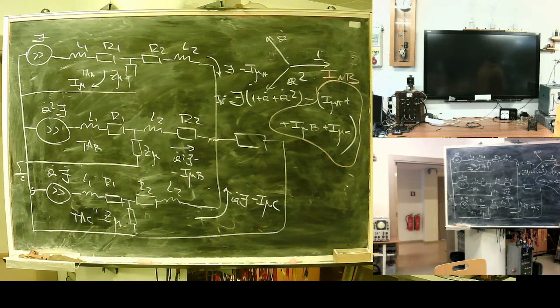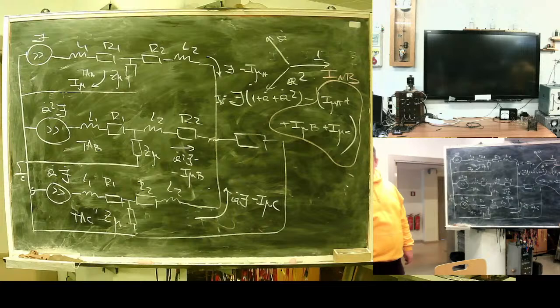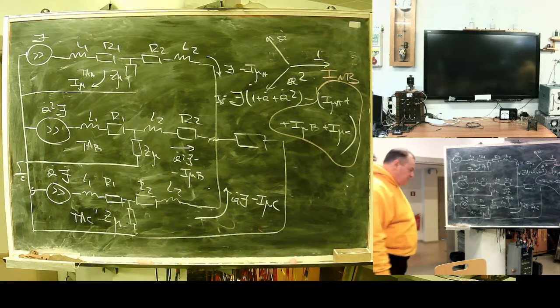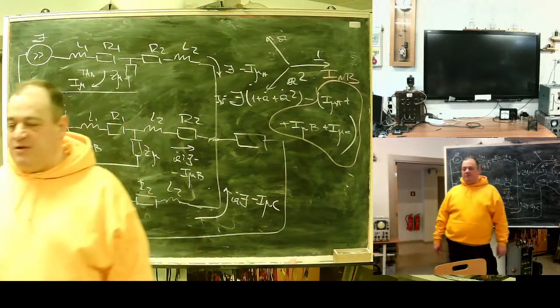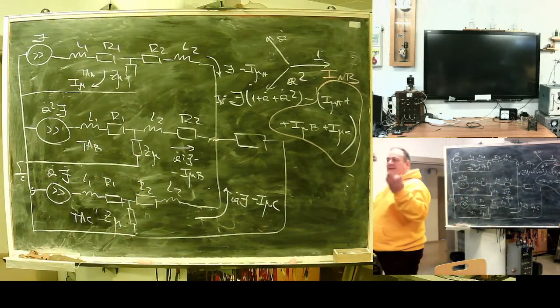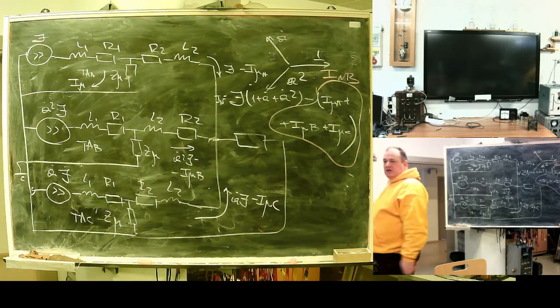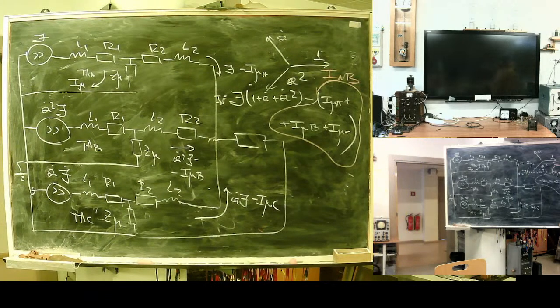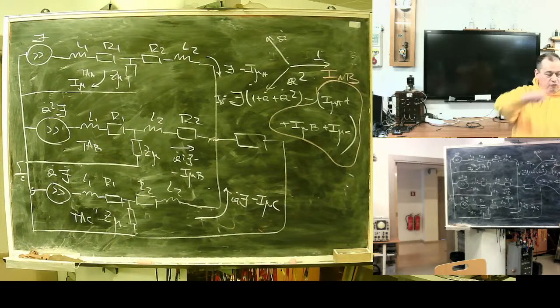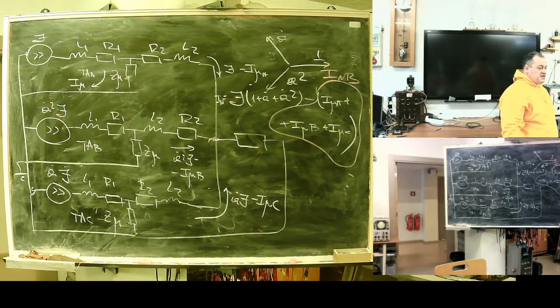There are no absolutely uniform current transformers in this world. A bit different assembly of core, a bit different steel. Even if you take one sheet of steel, it will be thinner on the side and a bit thicker in the middle, because the rollers of the roller press were like this. Sometimes roller presses are adjusted a bit incorrectly, and they press like this. So this means that one side will be thick.